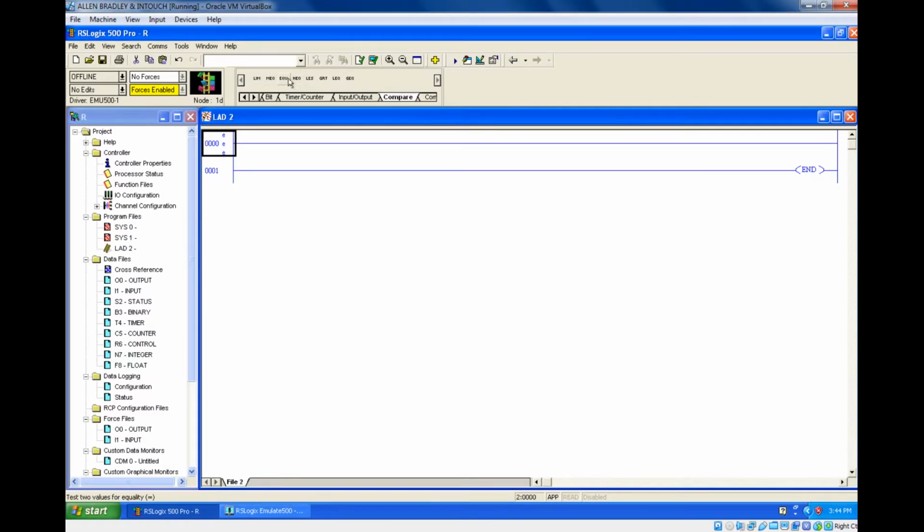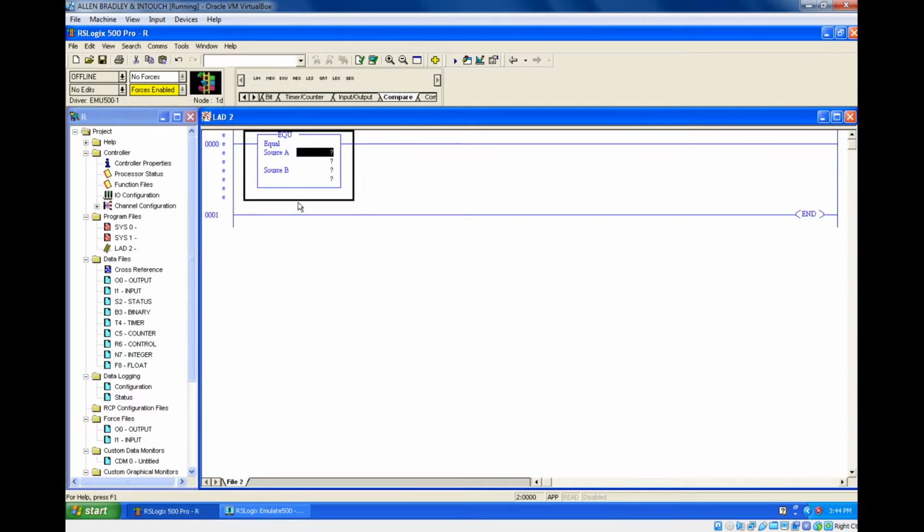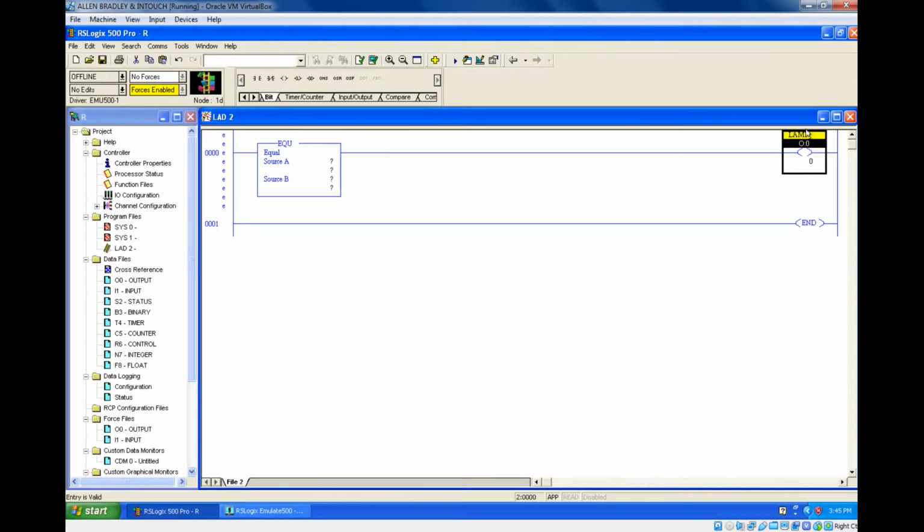So here, these comparator instructions are input instructions. So what does that mean? You're supposed to connect one output here. See, I'll just take this equal block. Can you see? It will be coming over here. That means you're supposed to connect the output coil, because the output of this instruction will be reflected in this coil. If it is true, the coil will be on. If it is false, the coil will be off. So let's give an output address for this lamp, right?